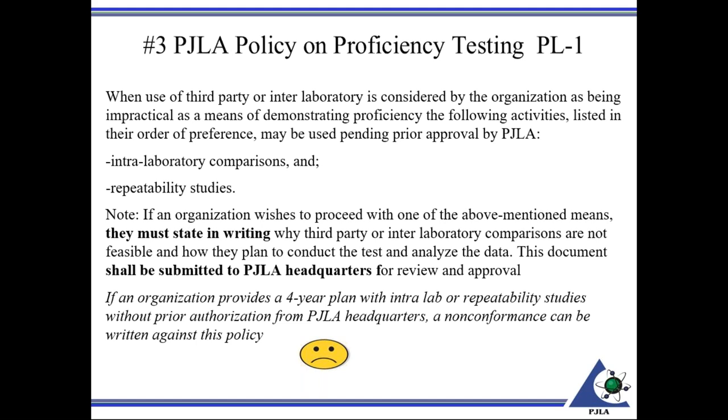And when I'm speaking about an intralab test, that's done within the confines of your organization. So for example, if you have technician A, B, C, D, say A was the senior technician, they would run a test or calibration, and B, C, D would follow, and you would compare the results to perhaps a reference value that was established within the lab. Repeatability studies, that's basically what it is. That's the bottom of the pecking order. Perhaps it's basically repeating the measurement, seeing if you can repeat it. The biggest problem with that I see is, yes, you could be repeated, but are you repeating the right result?